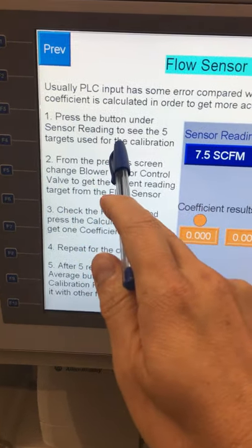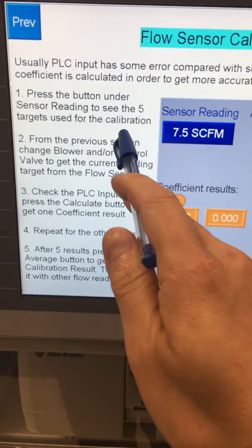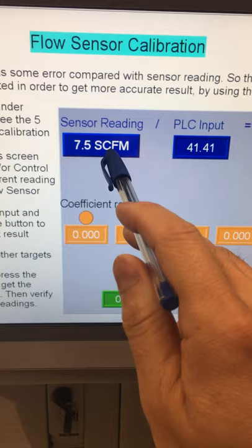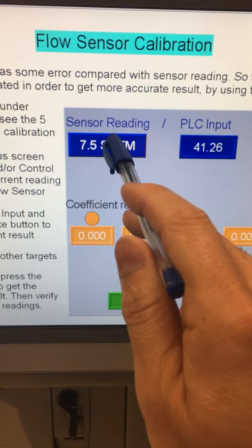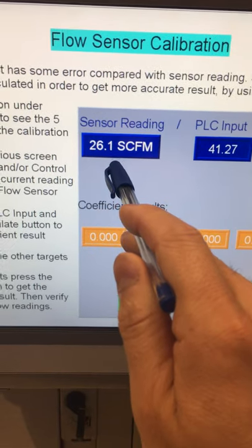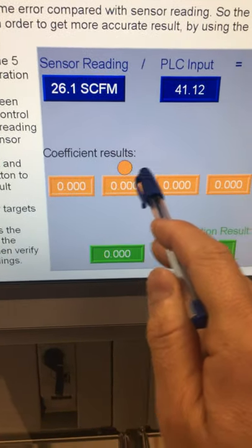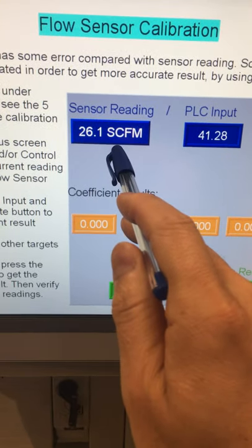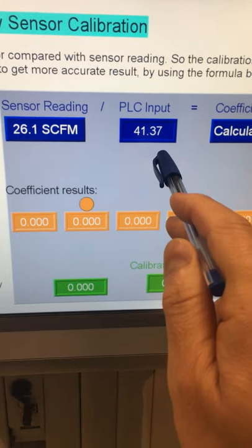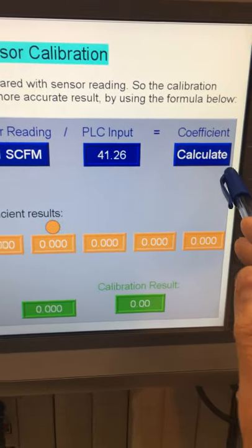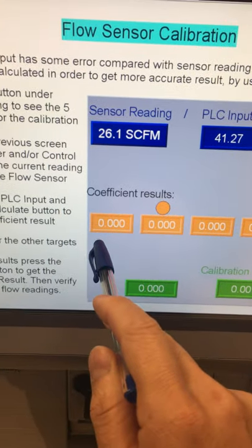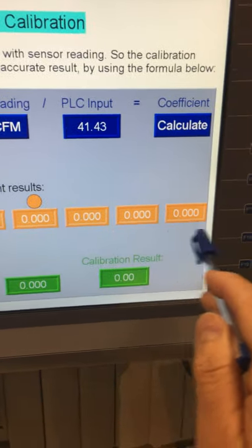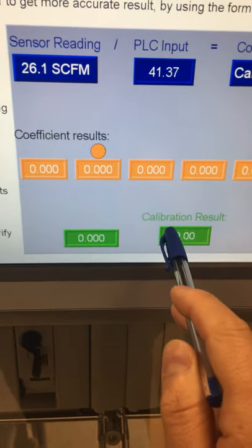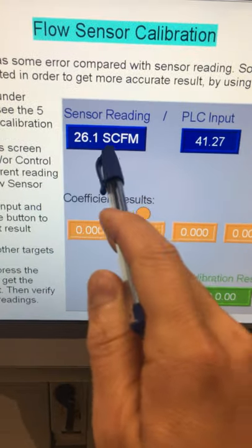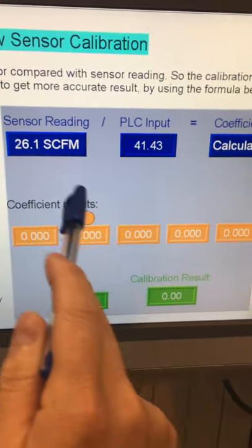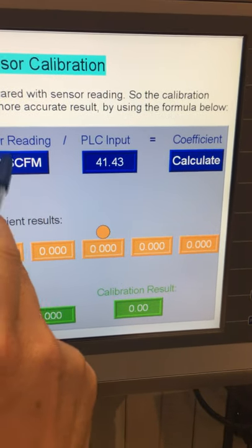Press the button under the sensor reading to see the five targets. We need to set up the flow sensor on five targets. So right now it's 7.5. If I press this, then you will see the next target should be 26.1, right? You can see the indicator on the second one. Whenever we get the sensor reading on a target, the PLC will have an analog input. If we use this formula to calculate, we can get a factor coefficient, right? We need to get five of them, then calculate the average. That's the whole process we need to do. If you keep pressing this button, you will see the indicator go to the next one. So those are the five targets we need to calibrate.